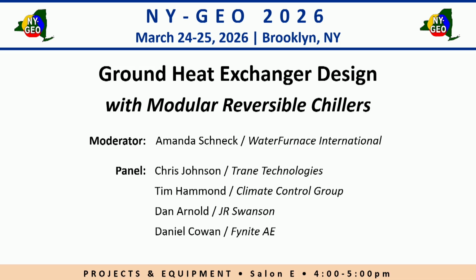Please. Okay, so another thing that I heard today, and I've been in this field a while, is that I've heard lots of times that if we undersize the bore field, it's going to heat up over time, and I think that's been a consistent problem in geothermal, that the field is undersized. What I heard today is that we kind of want to heat up the field before the winter, which I can understand heating it up a bit, but I heard like 90 degrees today. So if I heat my field up to 90 degrees and I'm trying to cool in the summertime with 90-degree water versus 50-degree or 55-degree water, that sounds like a fairly significant reduction in COP. So, I don't know, comment on that?